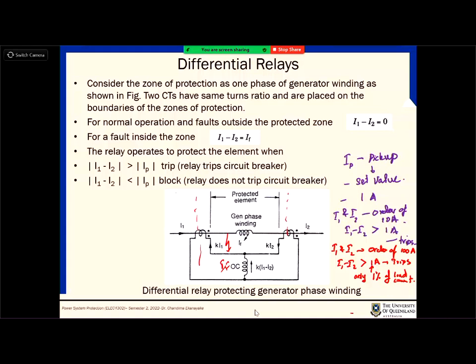Right? Got the point? When the load current goes up, if you keep your pickup current level as a constant value, let's say 1 amp, and then you change the load current, let's say the load current is decreasing, your rated current is coming closer and closer to the pickup current. Which means that the system will not be able to identify the small faults. The purpose of having a differential relay is that we want to identify the initial faults. They won't create, let's say, 10% of the load current at the initial stage. It could be 1%, it could be 0.1%. Small, low fault currents, right? But with this scheme, it is hard to identify if you just look at the absolute pickup values.